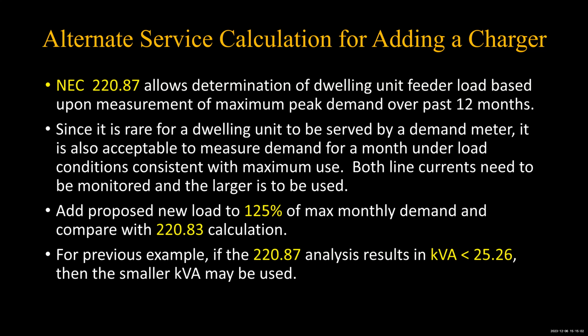And by the way, most chargers are adjustable. So you buy one charger and you can tell it what rate you want to charge it at. We're going to plug it into a 30 amp, 40 amp, 50 amp, 60 amp, 70 amp, 100 amp circuit. And that means 100 amp circuit breaker, and it will decide inside. There's interesting things about changing that. And of course, if you change that, the price you pay is to pop your main breaker. You don't want to do that, so you want to make sure you set the demand of your system to something that's going to maintain the integrity of your circuit. And of course, the AMI is going to do it for you. So anything of kVA less than 25.26, if you use 220.87, then you'll use the 220.87 calculation.